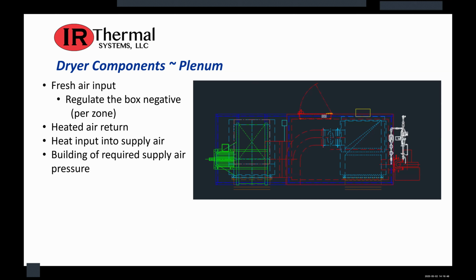Looking at the individual components, the plenum is probably one of the most important because it has the highest level of sophistication for the componentry involved, with the gas train and the burner control system. That's if it is a natural gas system. It can also be steam or hot oil or indirect natural gas fired, but it's still where the most componentry is located. You'll have the supply fan, which might have a high temp limit switch to make sure the fan's running on safe conditions. Also, pressure transmitters to understand what my supply pressure is.